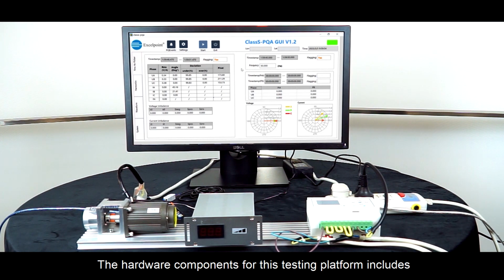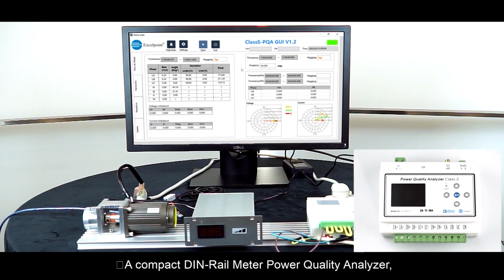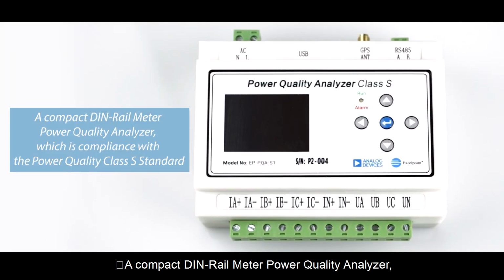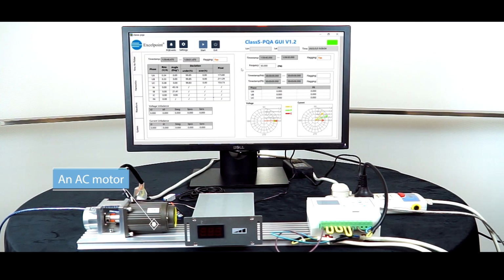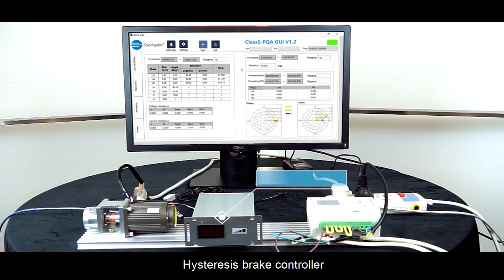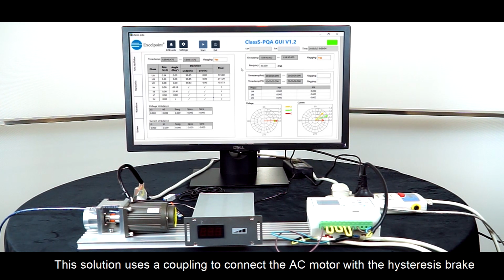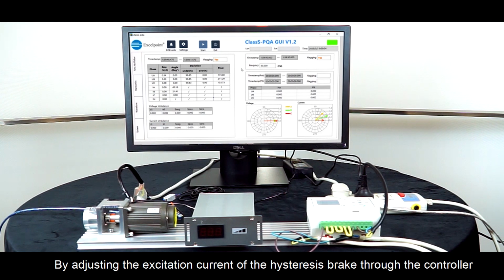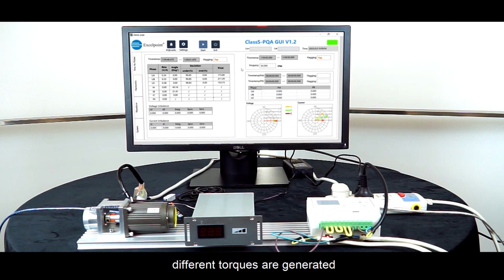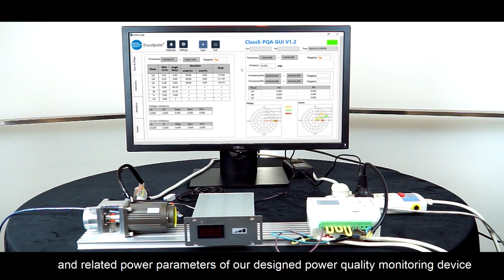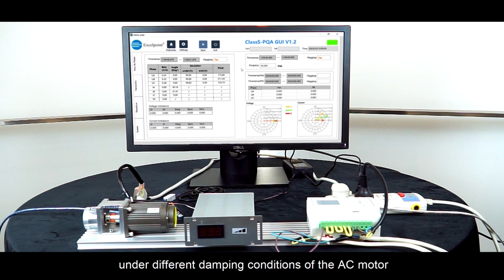The hardware components for this testing platform include a compact DIN rail meter power quality analyzer, which is compliant with the Power Quality Class S standard, an AC motor, and a hysteresis brake controller. This solution uses a coupling to connect the AC motor with the hysteresis brake. By adjusting the excitation current of the hysteresis brake through the controller, different torques are generated. This is used to demonstrate the changes in harmonics and related power parameters of our designed power quality monitoring device under different damping conditions of the AC motor.